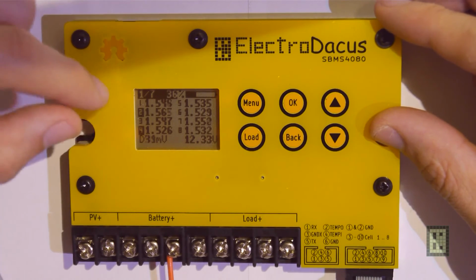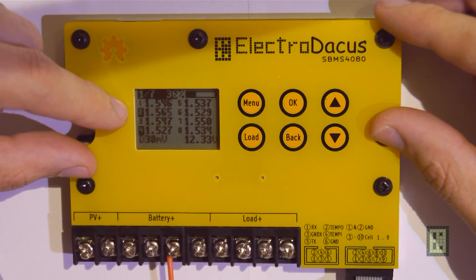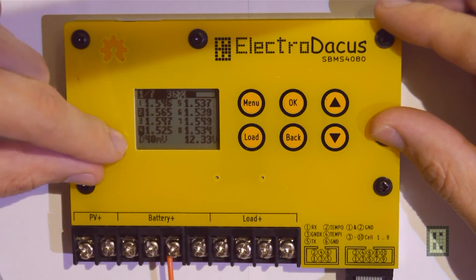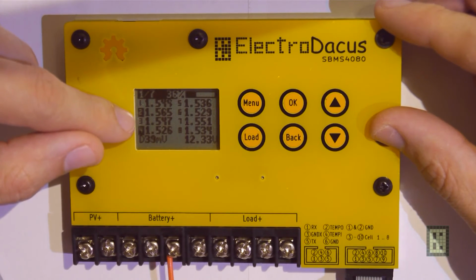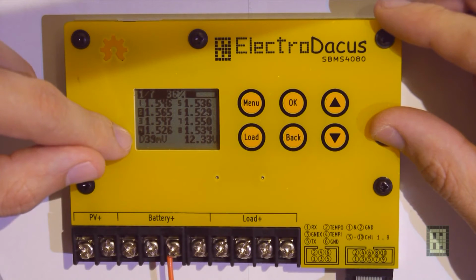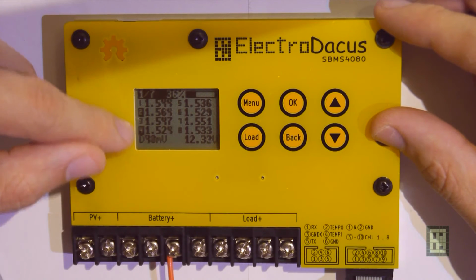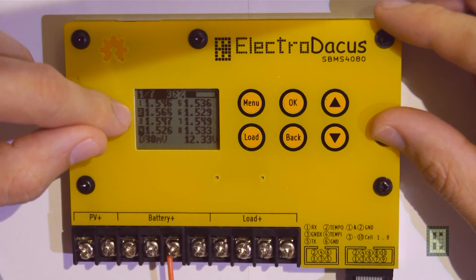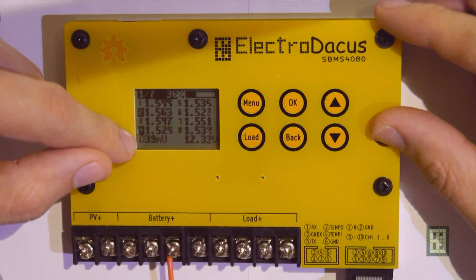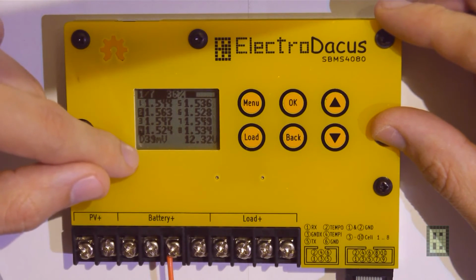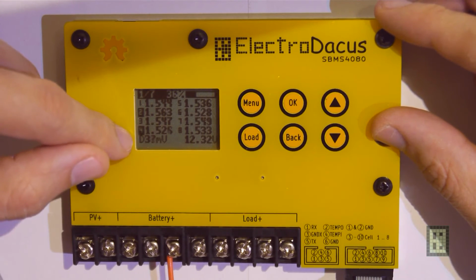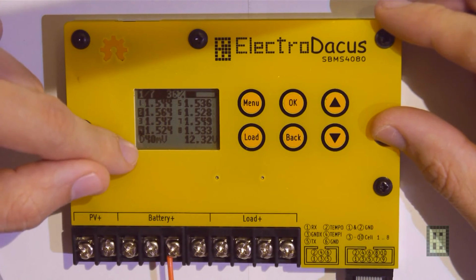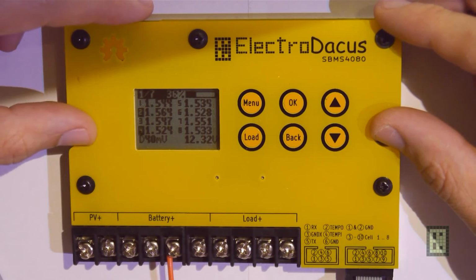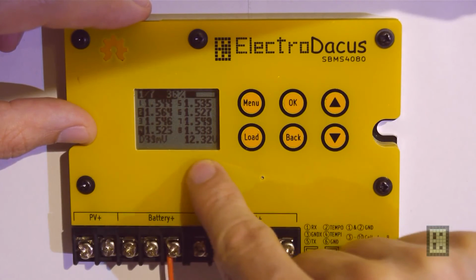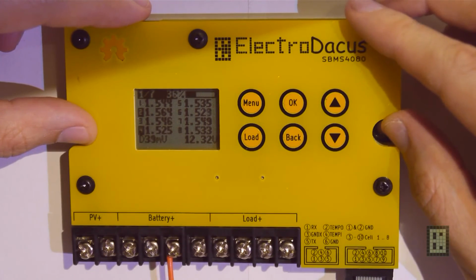Then there are individual cell voltages, and you see cell 2 and 4 are highlighted because these two are the highest and the lowest cell. Cell 2 is the highest and cell 4 is the lowest. Then you get the delta between the minimum and maximum cell, which is around 40 millivolts right now, and the total battery voltage, which is 12.32.